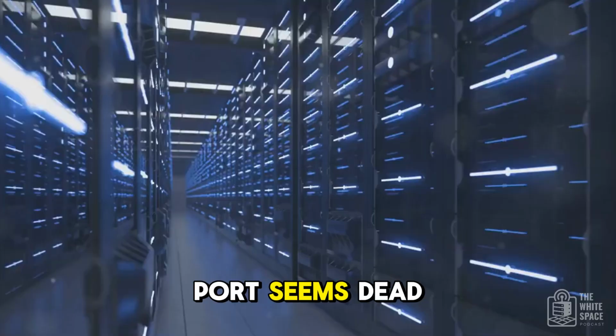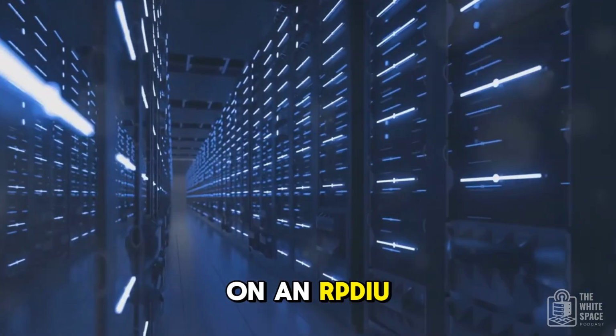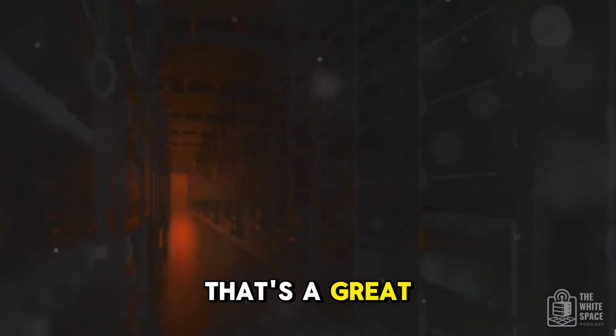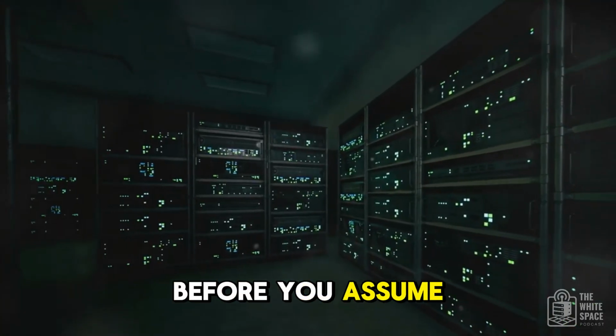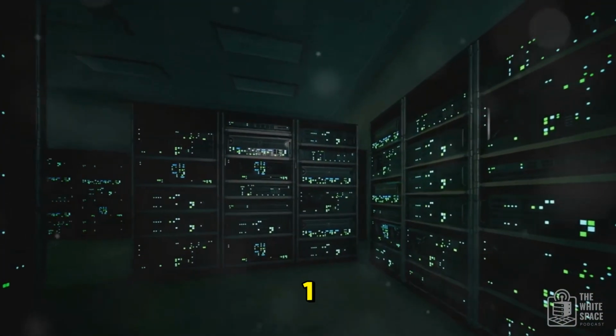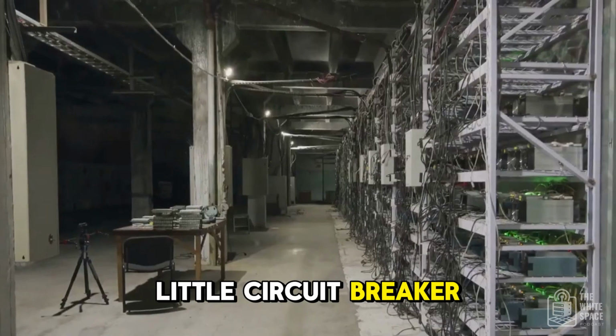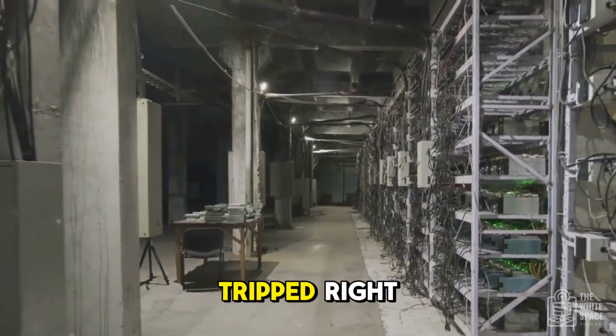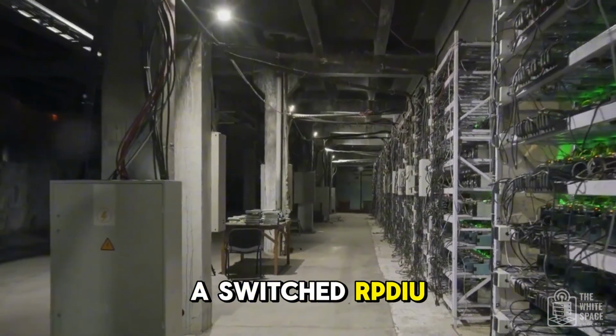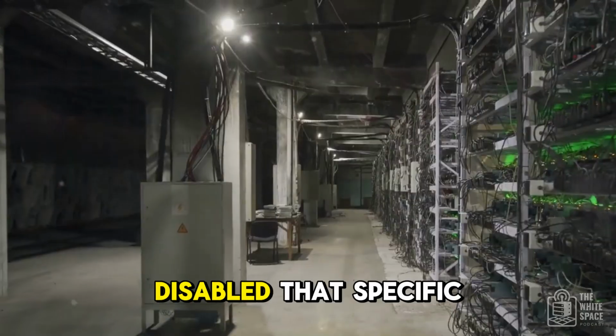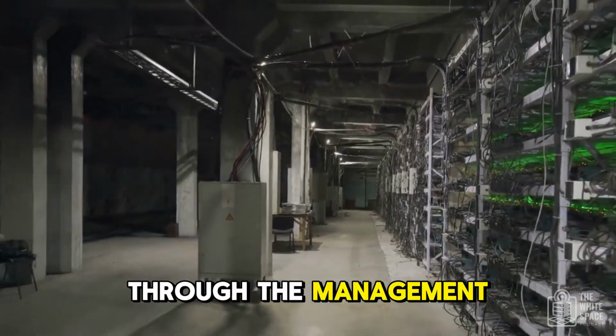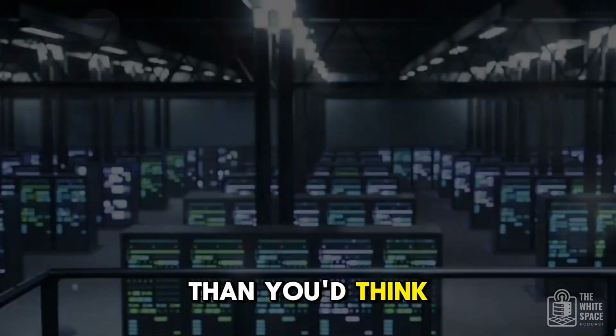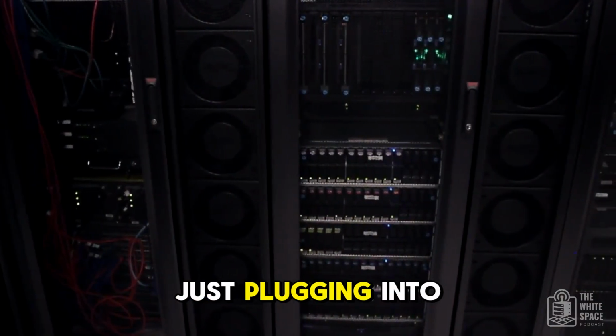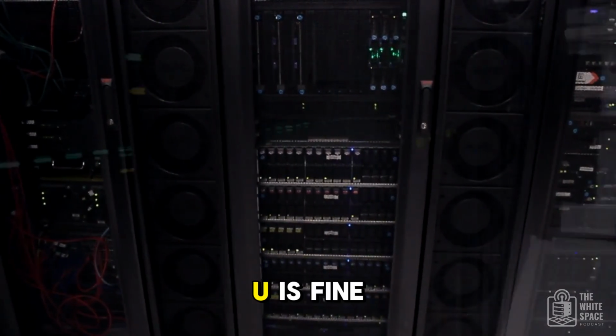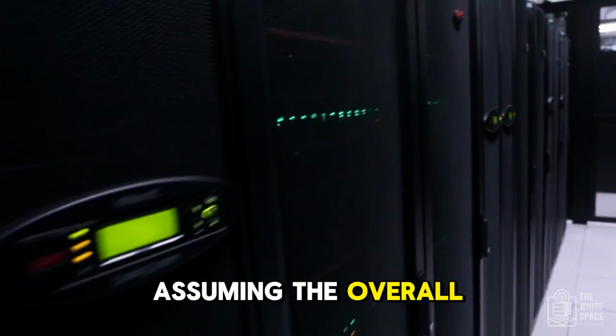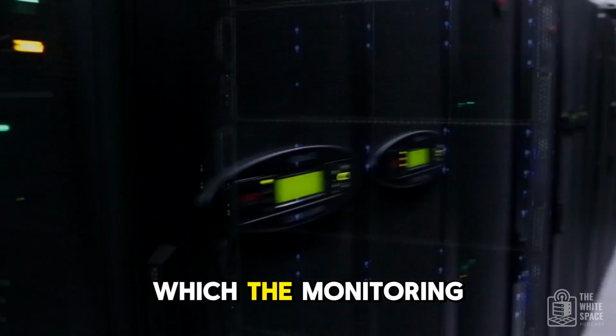So if a port seems dead on an RPDU, it might not be broken. Exactly. That's a great practical tip. Before you assume the RPDU is bad, check two things. One, is there a little circuit breaker on the RPDU itself that might have tripped? Right. Two, if it's a switched RPDU, could someone have remotely disabled that specific outlet through the management software? Happens more often than you'd think. Good tip. And usually just plugging into another free outlet on the same RPDU is fine. Perfectly fine, assuming the overall PDU isn't overloaded, which the monitoring should tell you.